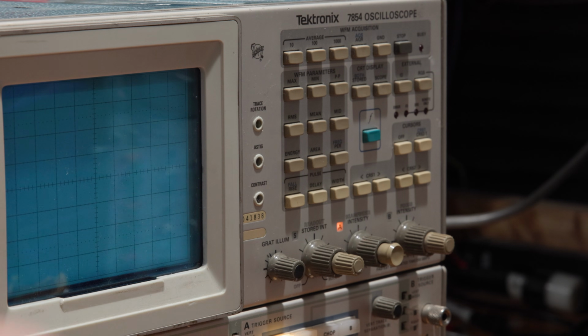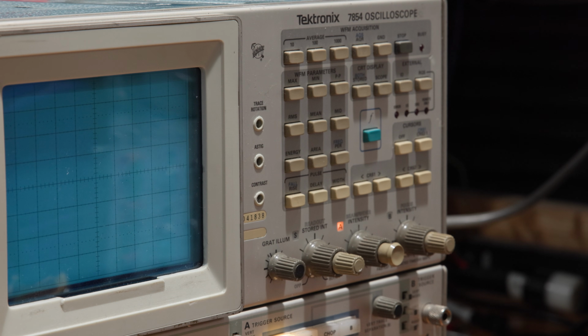Contrast is a front panel control, so we're going to leave that set as is for right now. And I'm going to put the cover back on the Z-axis board because we are done with the Z-axis board at the moment, and we're going to get into geometry and alignment, but I need to rotate the scope 90 degrees so we can actually see the front panel, and I don't want all the high voltage stuff hanging off the back of the board. So we'll get that buttoned up, and now it's going to get into the important alignments and calibrations due to the fact that we had display problems, and we are about to tackle display geometry and alignment and all that good stuff. So this is really where we should need to make some adjustments.